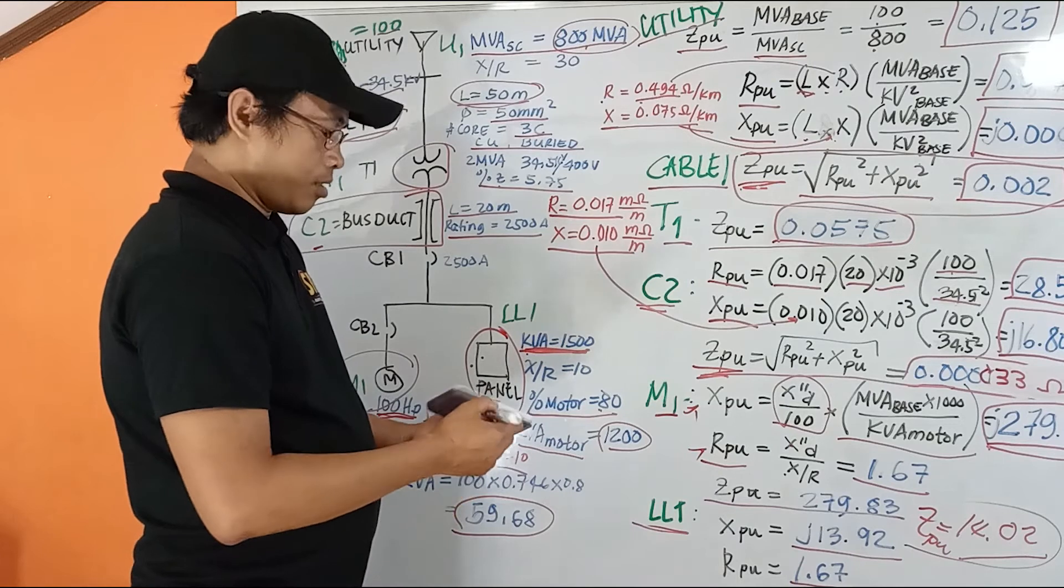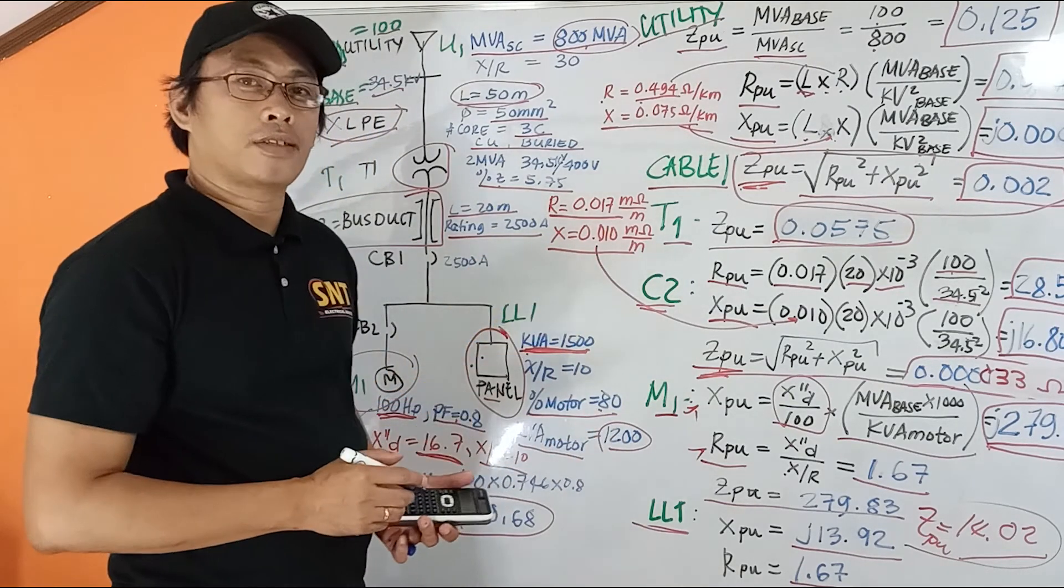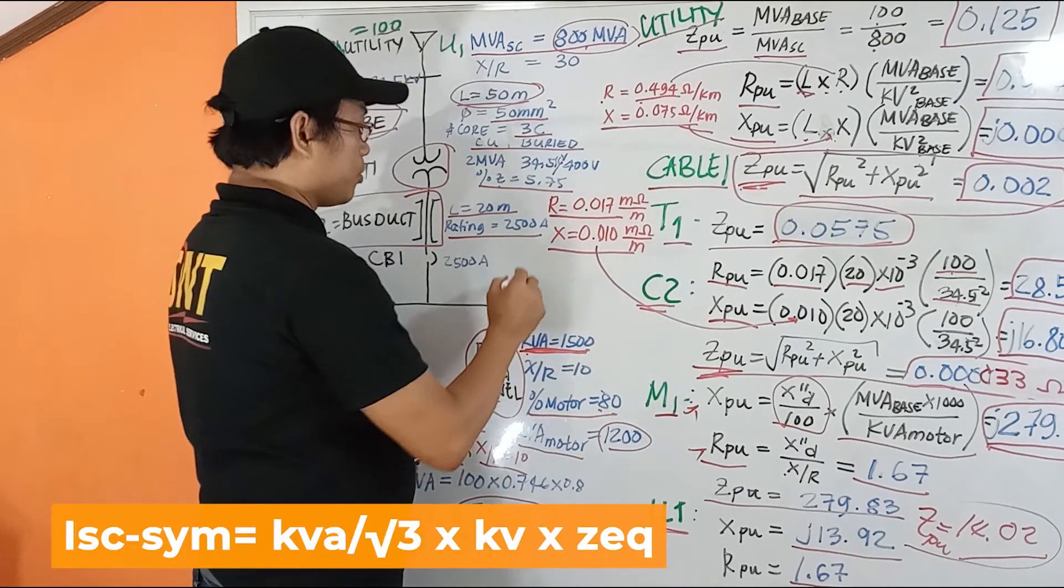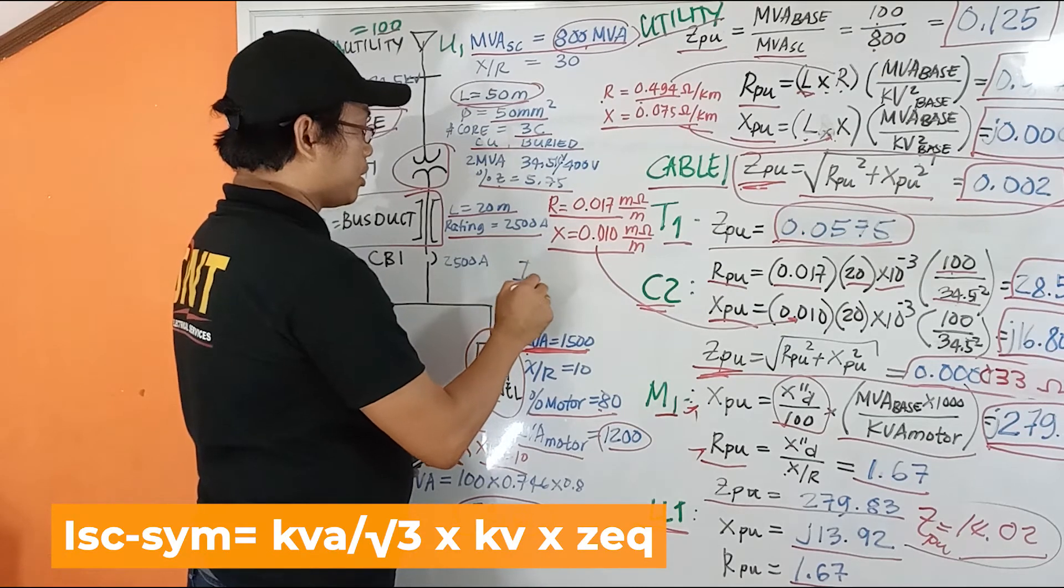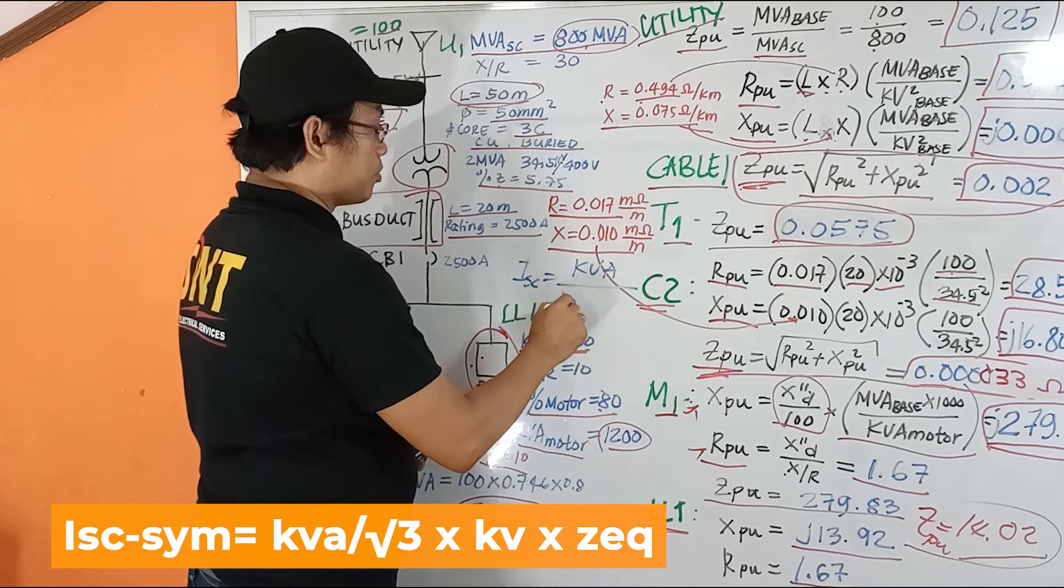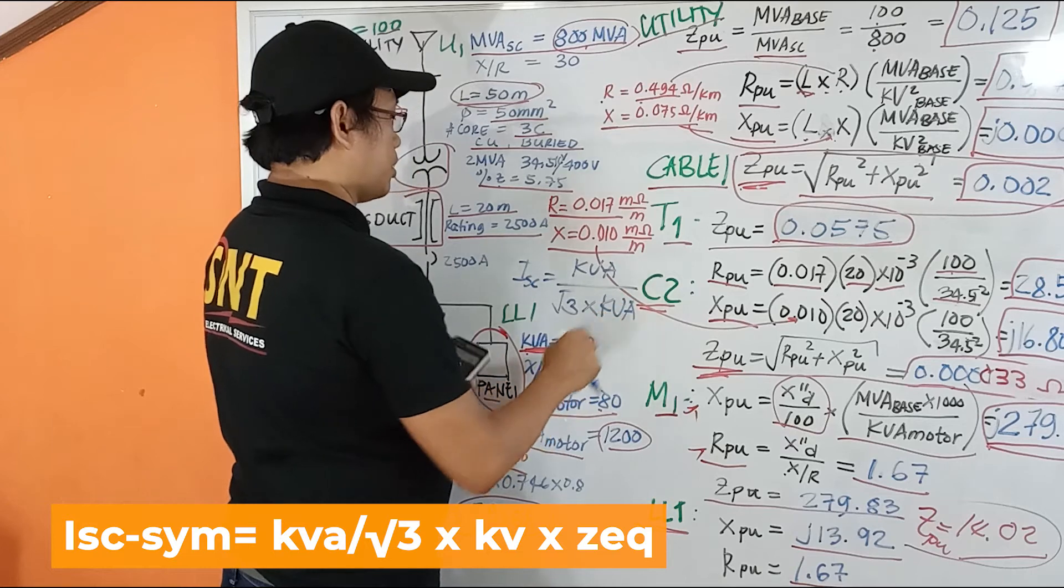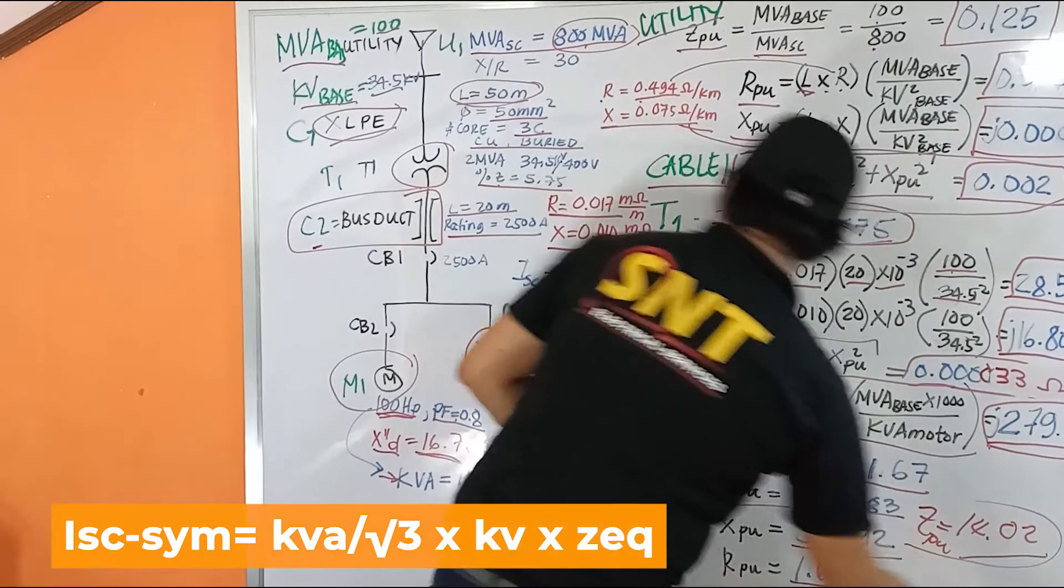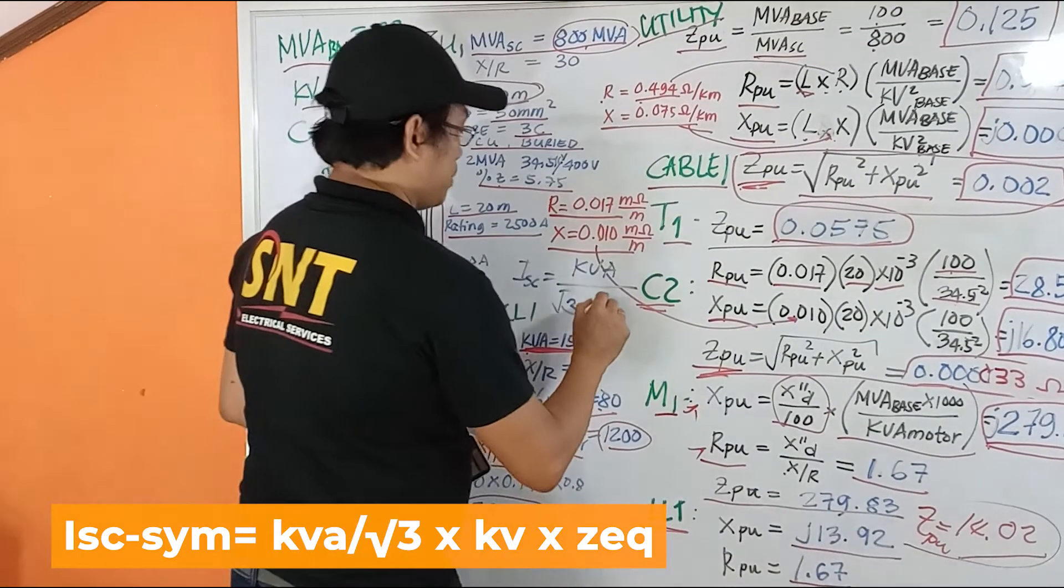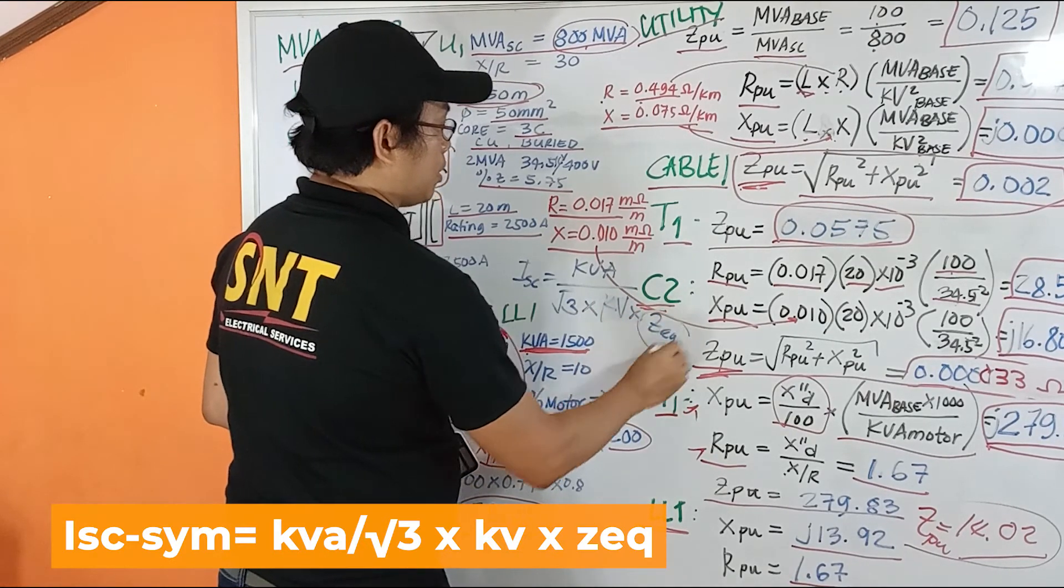So after that, we do the impedance analysis on our impedance diagram. At the end, we get to calculate the short circuit, which is the kVA over the square root of 3 times the kV times the equivalent impedance. Our goal is to get the equivalent impedance at a certain point.